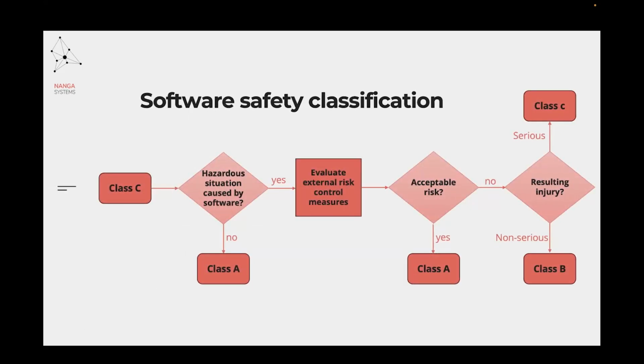How does the classification workflow look like? Software by default, according to IEC 62304, is always classified as class C. And we have to justify it in case we want to classify our software into a lower class. To do this, we have to answer a question first: is a hazardous situation caused by the software? In case the answer is no, then we can safely classify our software as class A. In case the answer is yes, then we have to evaluate potential risk control measures. And after the risk control measures have been evaluated, we can determine whether the risk is acceptable or not.